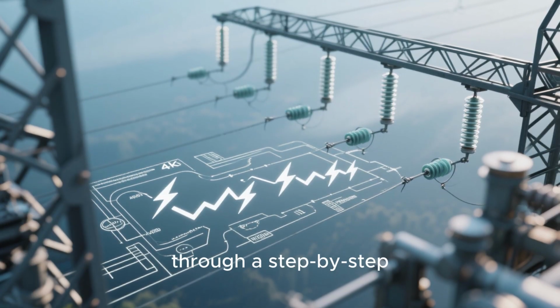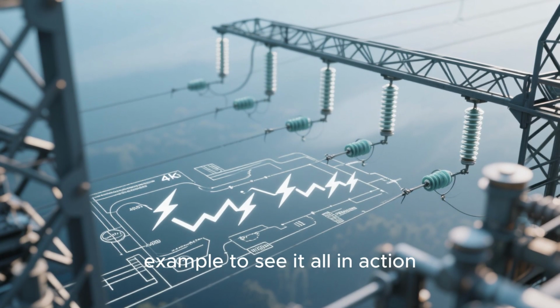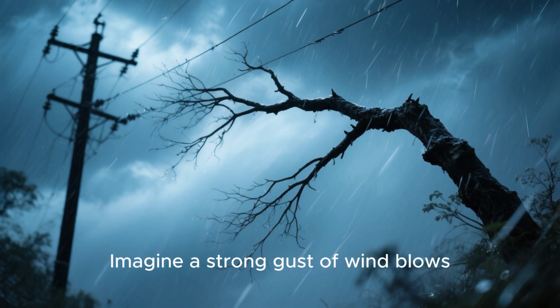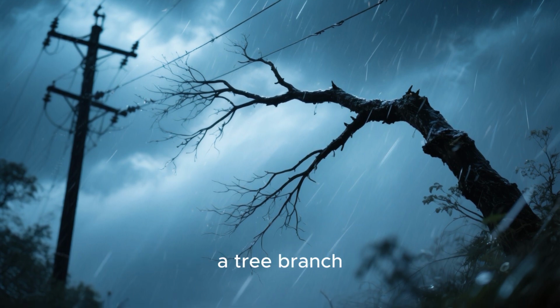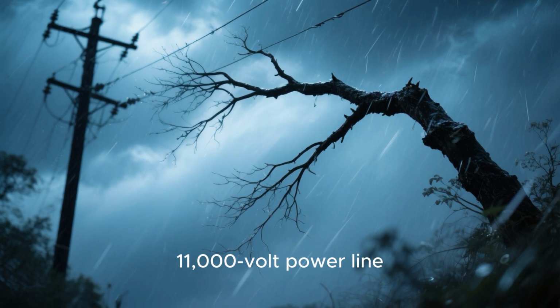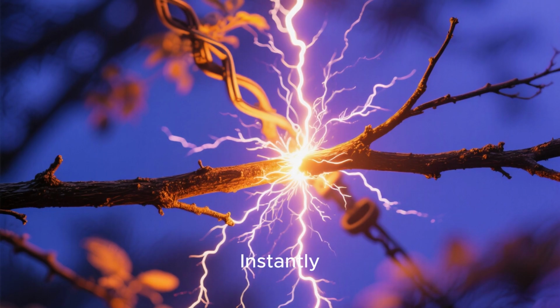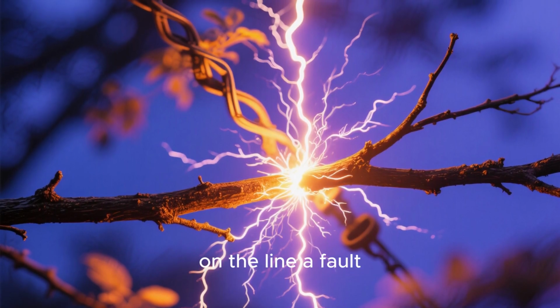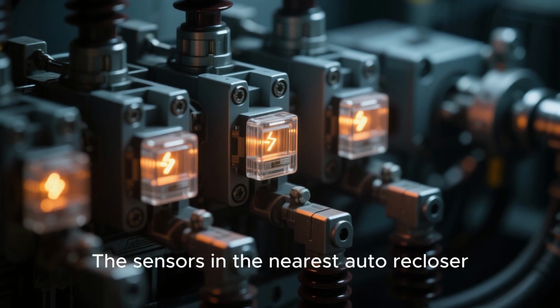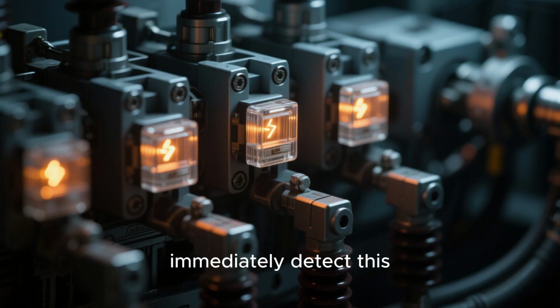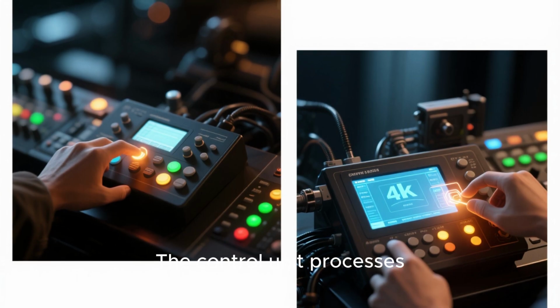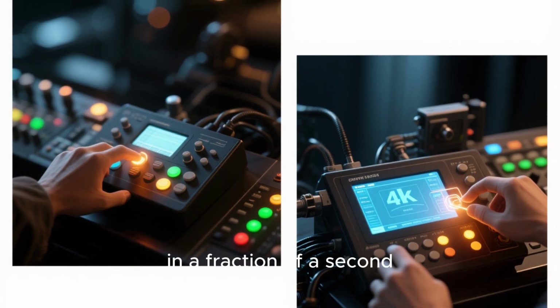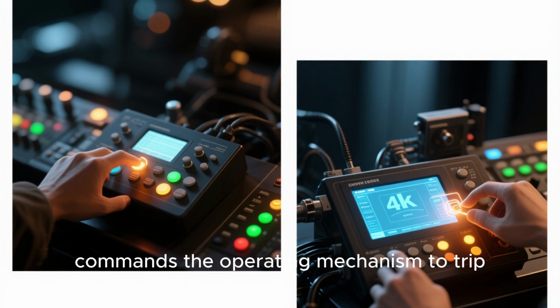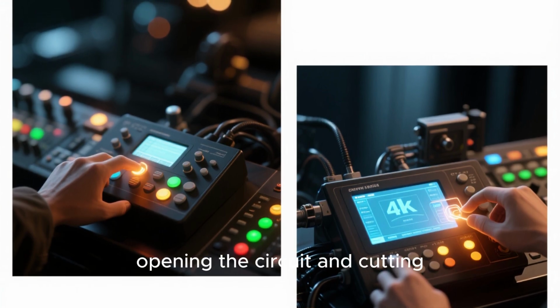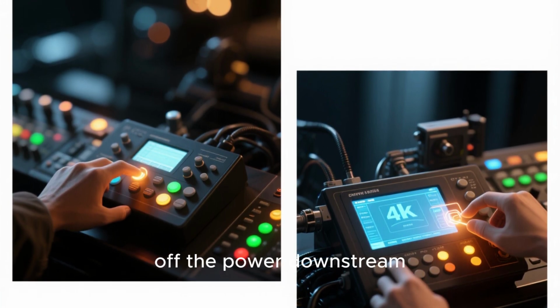Now, let's walk through a step-by-step example to see it all in action. Imagine a strong gust of wind blows a tree branch, causing it to touch an 11,000-volt power line. Instantly, there's a surge of current on the line, a fault. The sensors in the nearest auto recloser immediately detect this overcurrent. The control unit processes this information and, in a fraction of a second, commands the operating mechanism to trip, opening the circuit and cutting off the power downstream.